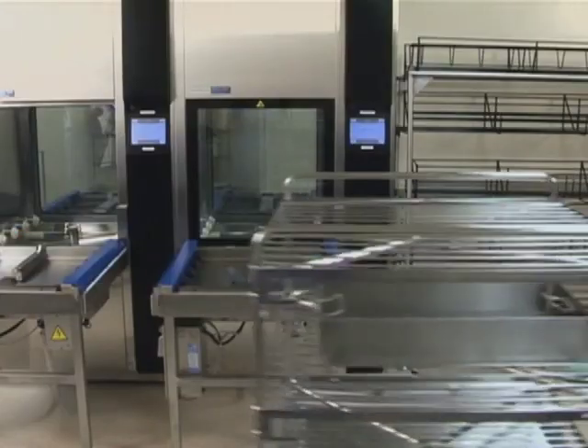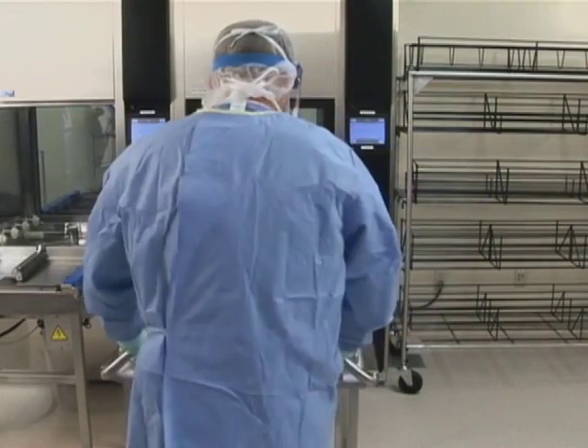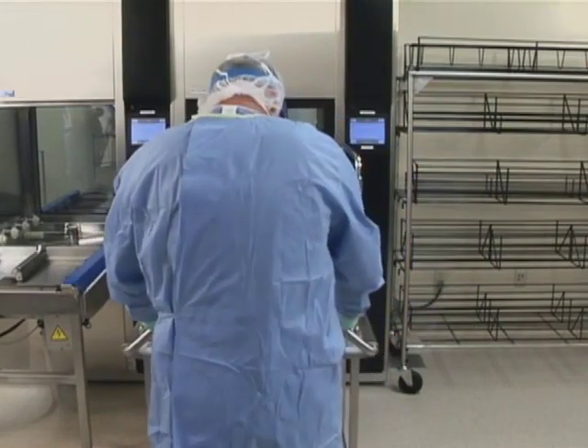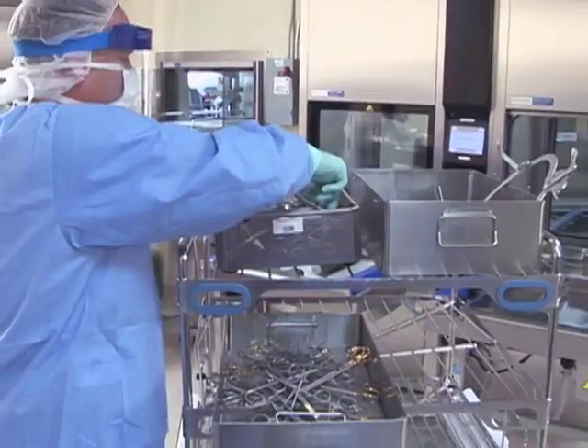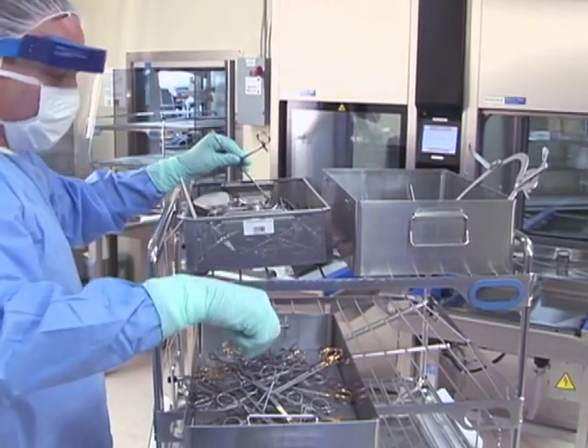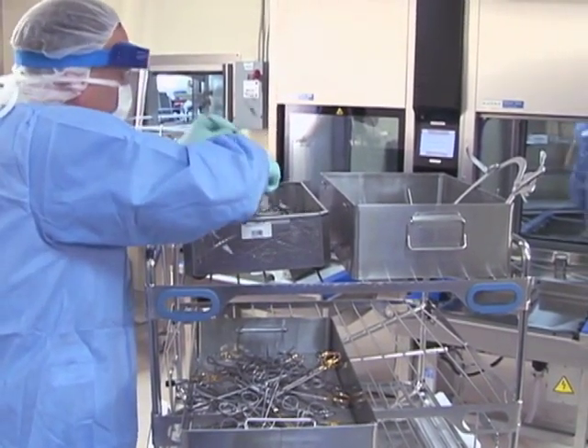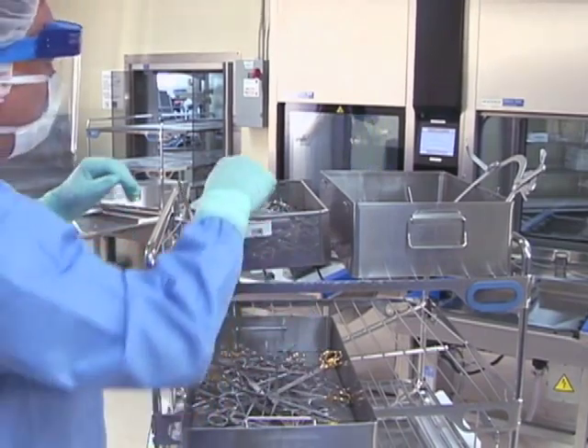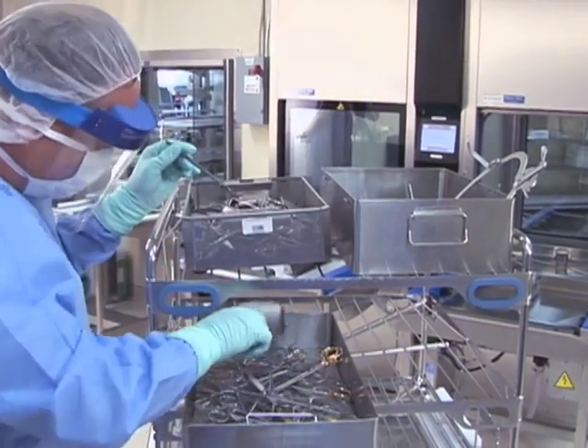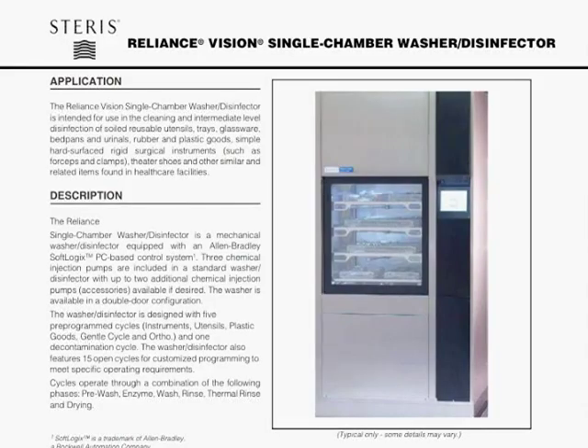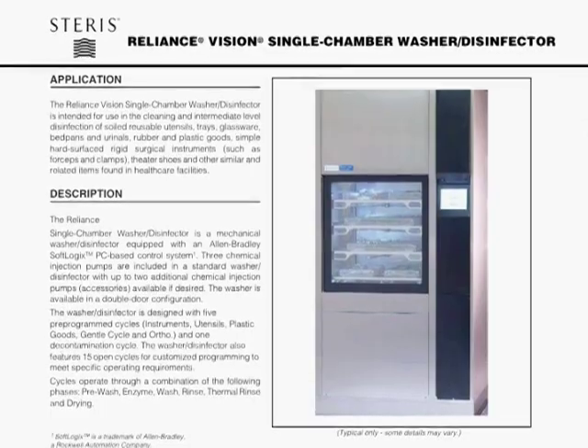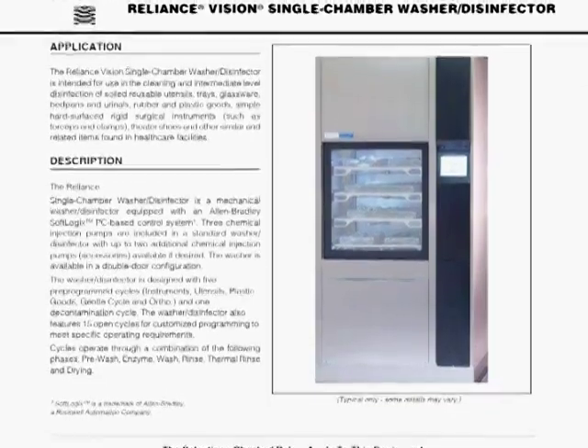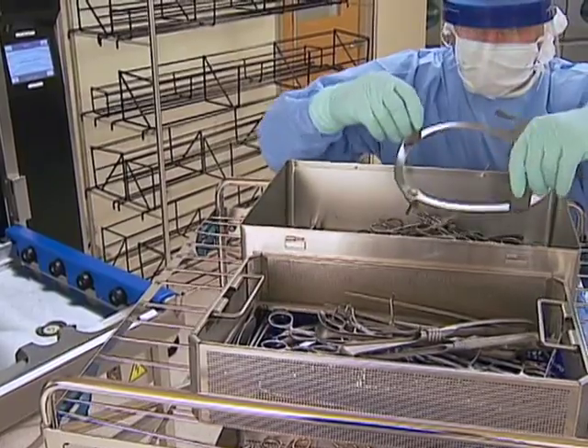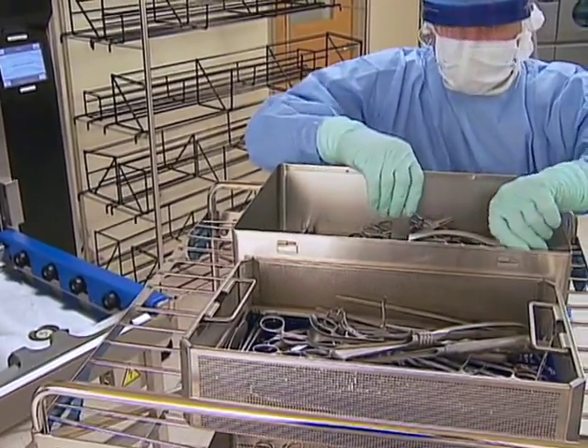Now you're ready to load the next rack to be processed. Close the chamber door and switch the cycle back to automatic. Use a rack that was designed for the types of instruments you're going to process. You should be using the Vision IntelliLoad manifold racks designed for STERIS washer disinfectors. Reference STERIS Tech Datasheet SD880 for complete rack details. Be sure that all instruments and devices are inside the tray.